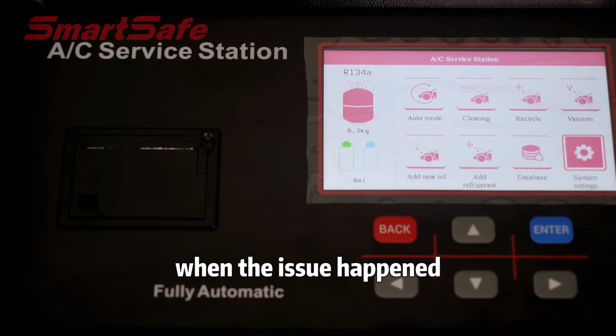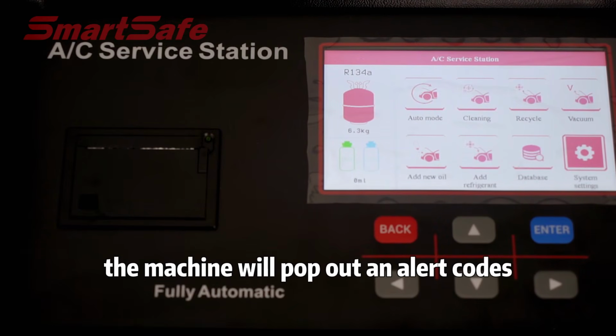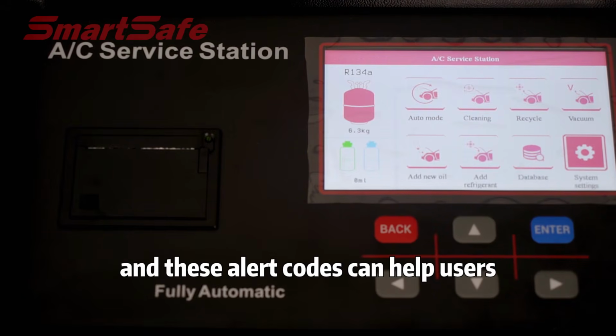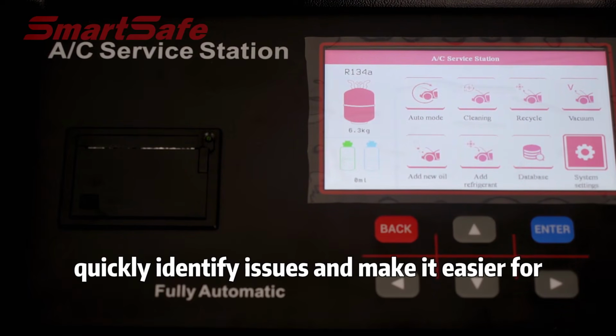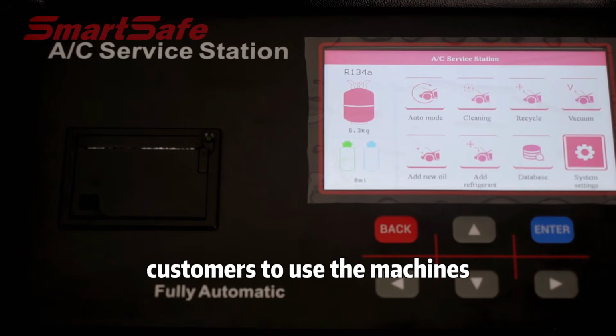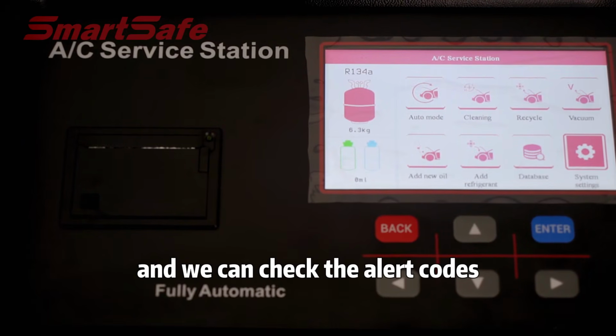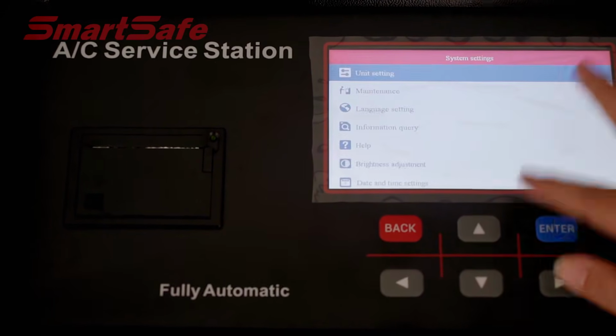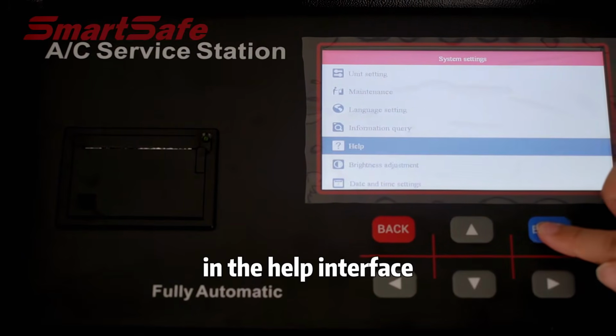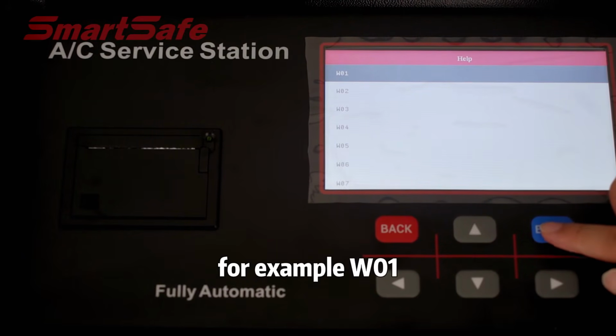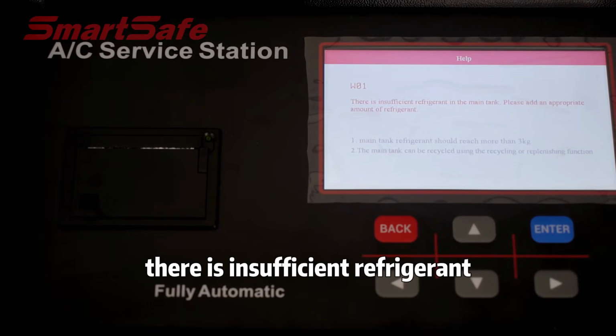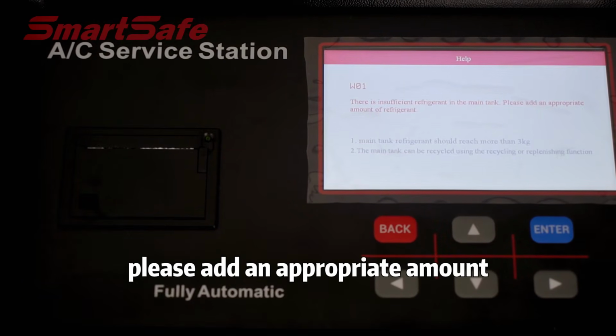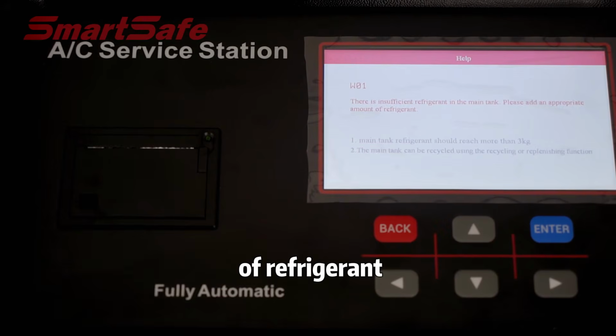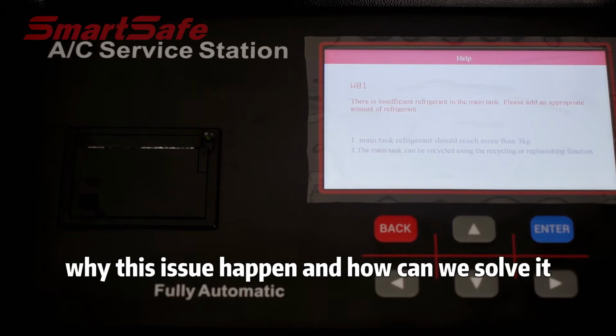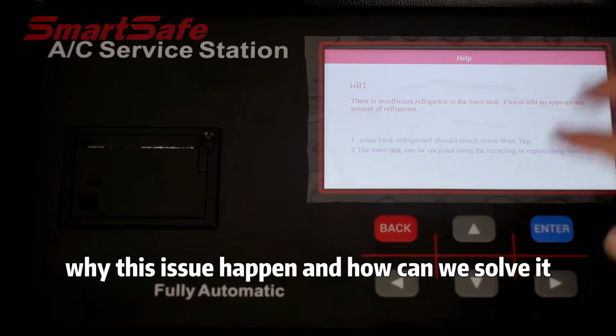When an issue happens, the machine will pop out an alert code. These alert codes can help users quickly identify issues, making it easier for customers to use the machines. And we can check the alert codes in the system settings. In the help interface, for example, W01 means that there is insufficient refrigerant in the main tank. Please add an appropriate amount of refrigerant. And below here, it shows why this issue happened and how we can solve it.